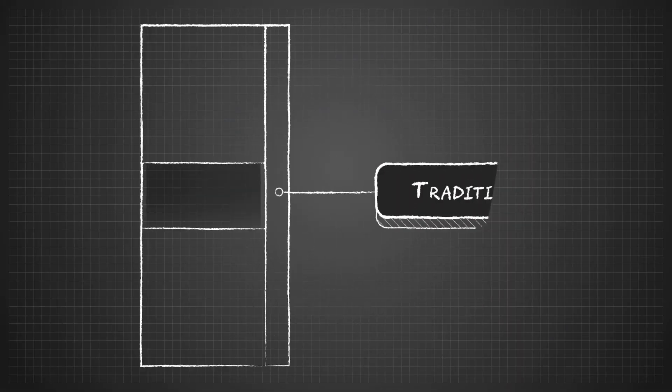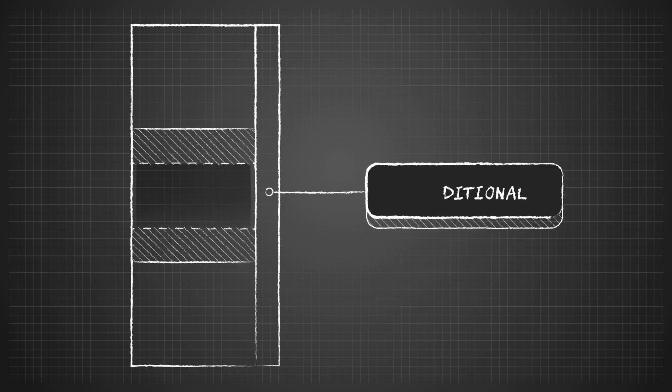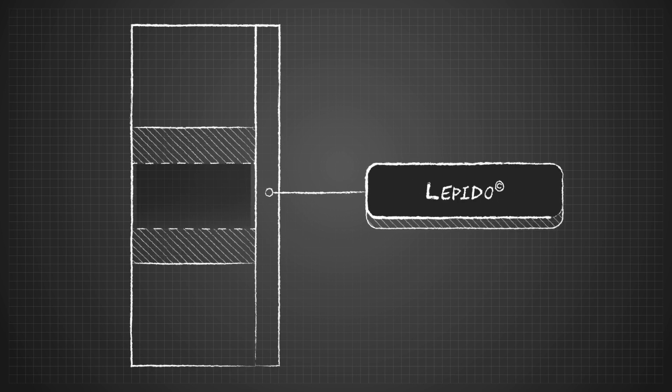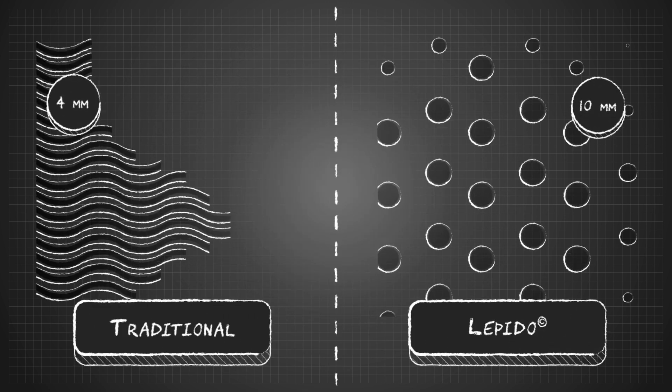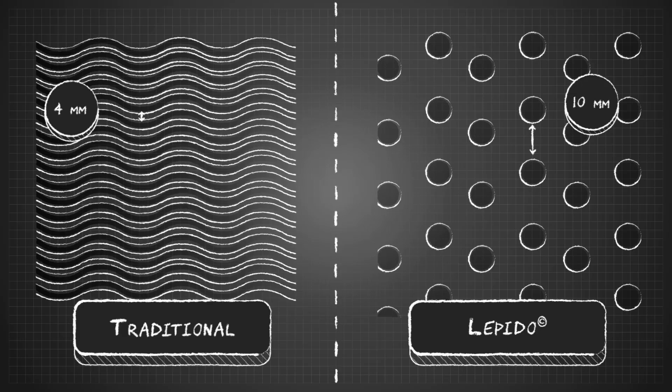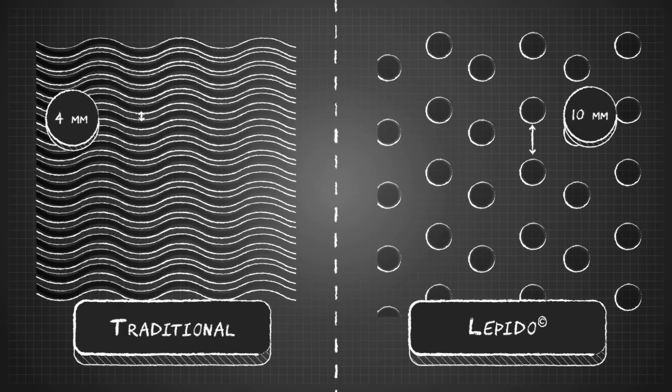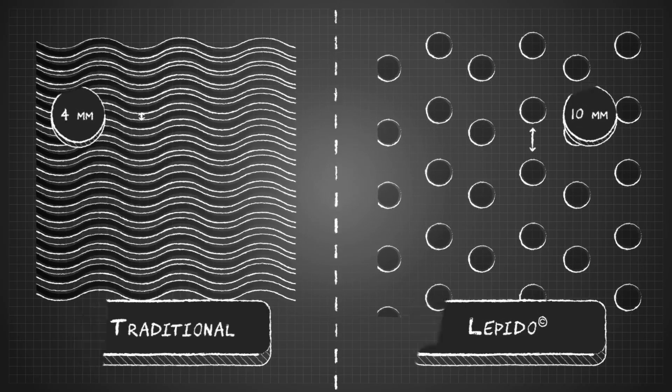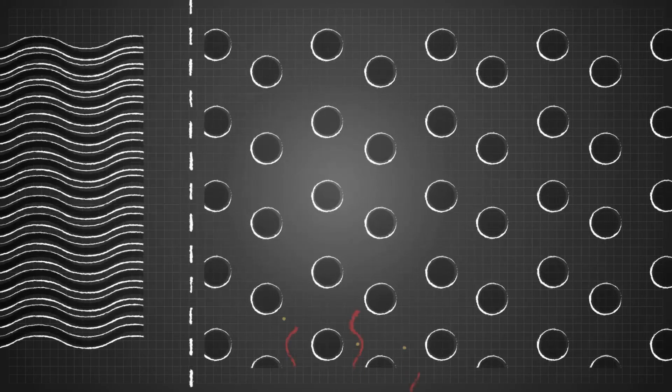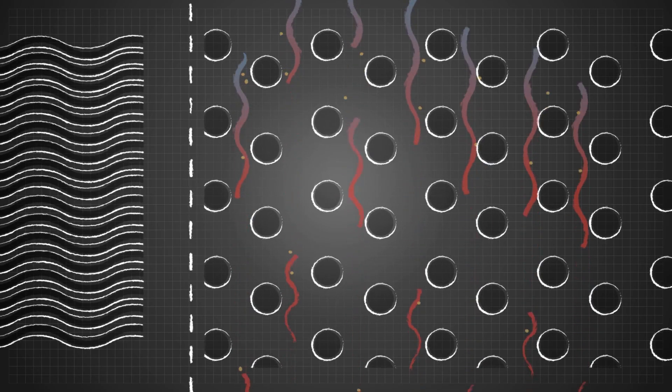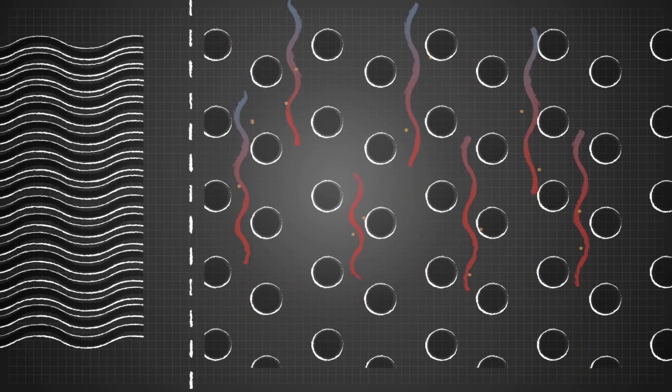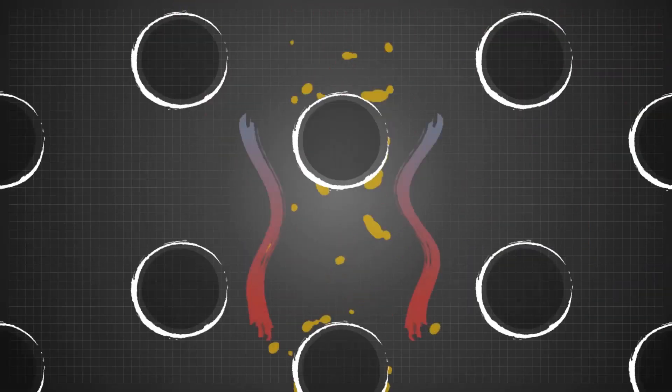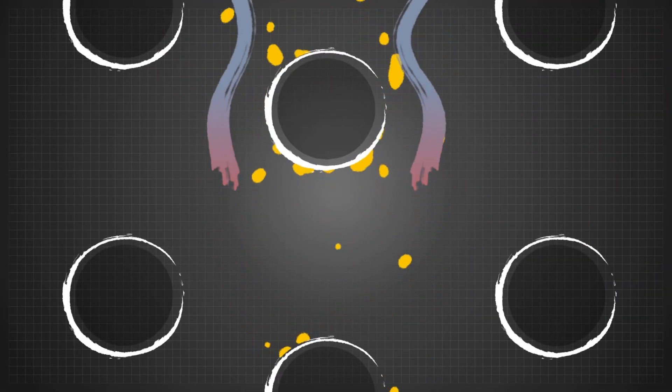Lepido being a heavy duty heat exchanger is larger compared to a traditional heat exchanger to make room for our patented geometry of the recovery coils. The space between the coils is much larger than between the fins of a traditional heat exchanger. The result is a unique airflow pattern where most of the particles can pass through the heat exchanger instead of sticking to the coils.